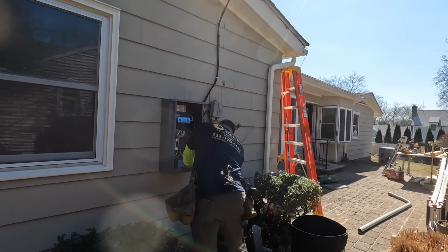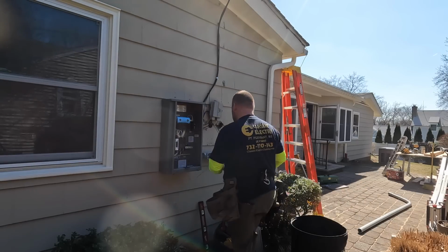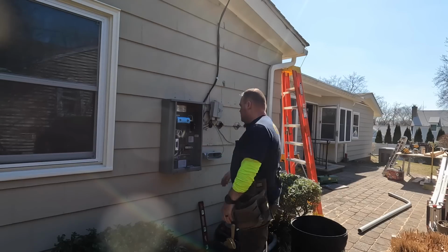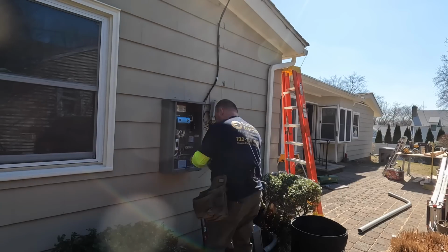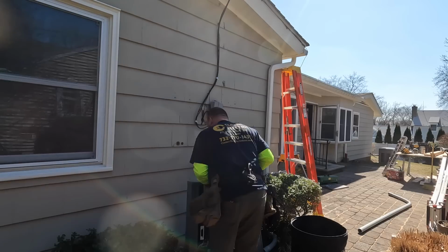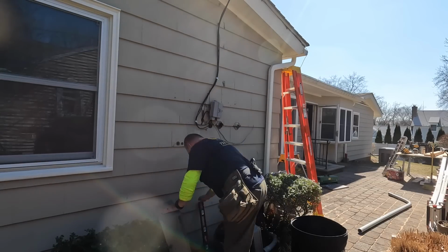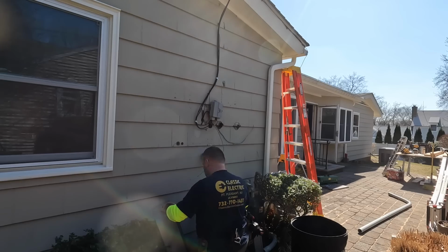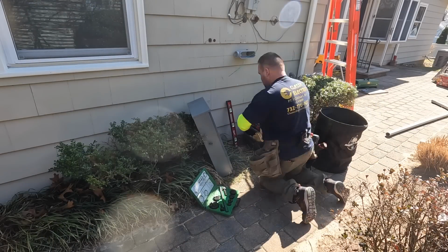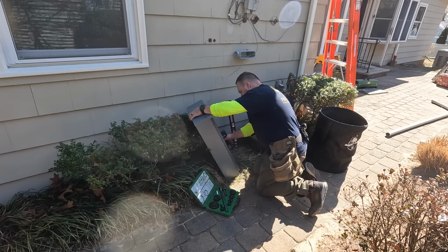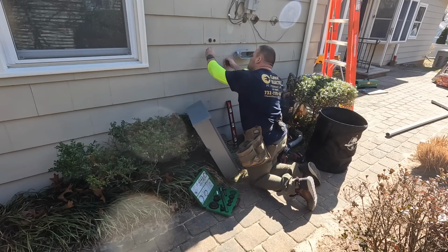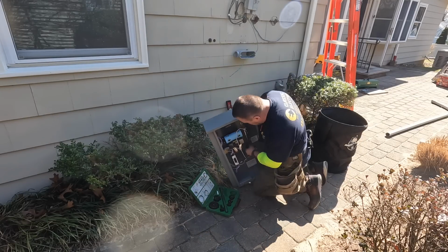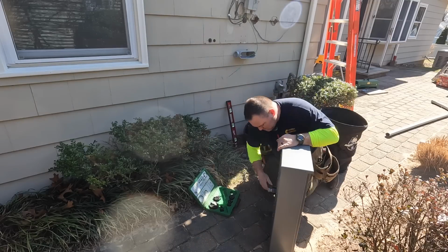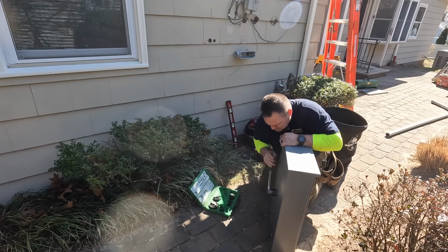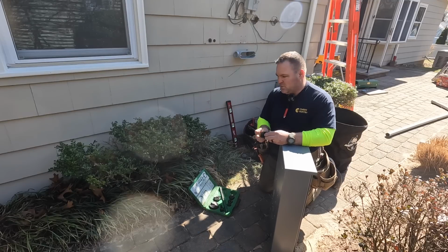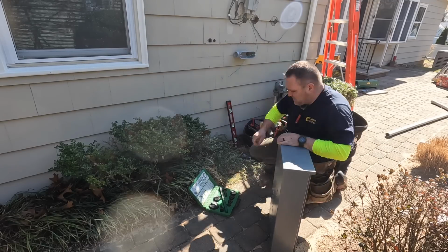So this here is a 200 amp automatic transfer switch by Kohler generator products. Mounting this, I wasn't exactly sure where I was going to go, but I had to figure - you can see those two holes back there, that's where the feeders for the generator go through the garage and then down into the crawl space, and the generator's over there at the far right of your screen up by the top. So just imagine this property: the garage here goes down into a crawl space and then comes back out to the generator.